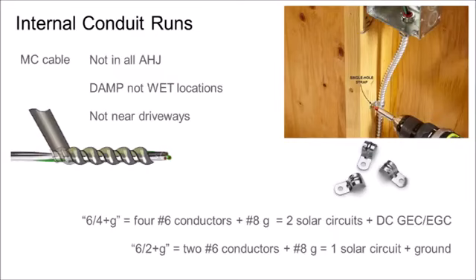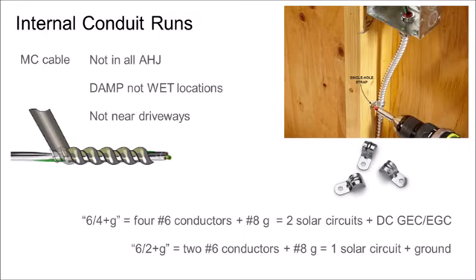DC conductors inside a building are required by code to be protected by metal conduit — not for grounding, but for physical protection of the cables. A rodent is less likely to chew a wire contained in metal conduit; a nail or screw is less likely to puncture a power cable contained in metal conduit. Some installers select micro-inverters specifically to avoid this metal conduit requirement, allowing the home run from the rooftop to be made in AC-rated Romex. Running metal conduit as a retrofit through an attic can be a difficult task.